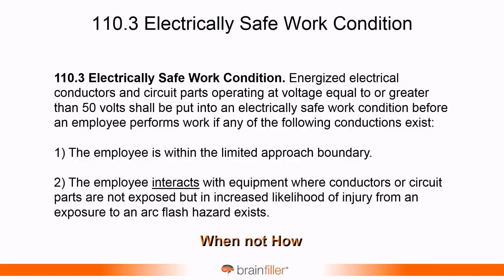2015 was the first time you started to see certain types of activities, operating a circuit breaker or a switch, doors closed and so forth. And then you also saw what is considered normal operation. And I'm going to talk about that in a little bit because there was an addition to that table about when an arc flash hazard may exist. And it has to do with the interaction side of this. And so the interaction, number 2, that's also equally important. And what I wanted to emphasize is this references when the electrically safe work condition is necessary, not how you establish it. That's later on in NFPA 70E.